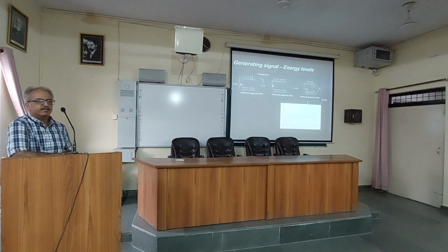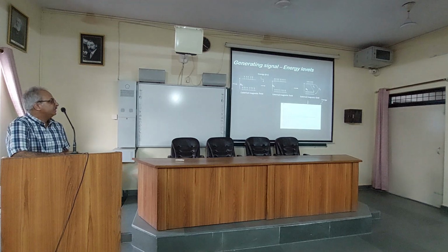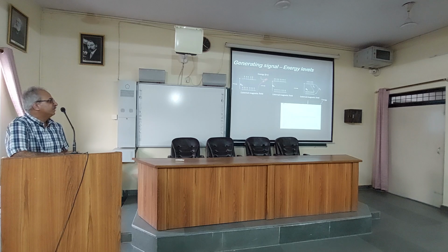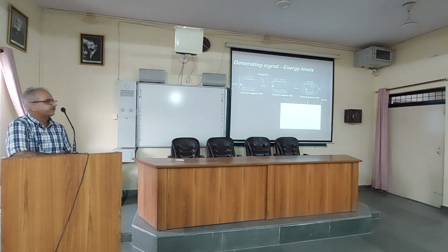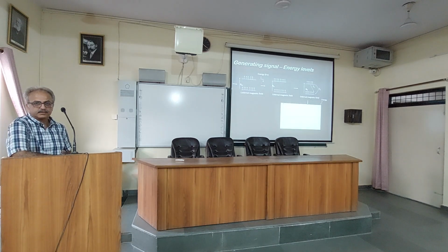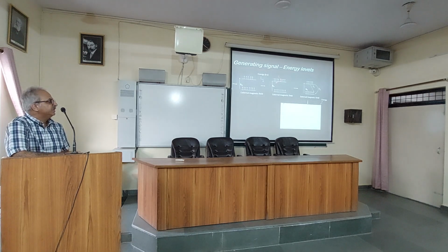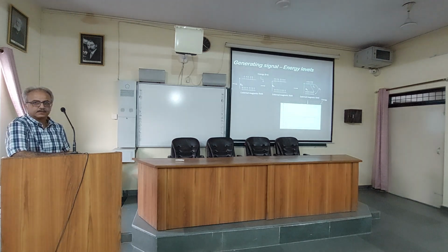In order to generate a signal, you have to give energy. That is the law of energy. Energy in NMR is given through what we call the radio frequency. So you give a radio frequency pulse, and you basically force some of these lower energy states to an unstable high energy state. The RF is given only for a few microseconds. It's not given for long. As soon as you release that, obviously these spins would want to come back to the steady state level. And that's precisely what happens.